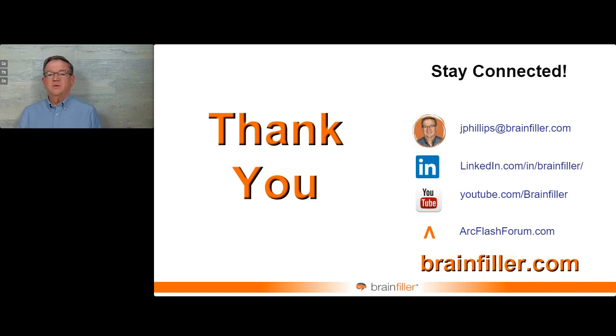Here's a really good one. There's currently a lot of virtual training replacing in-person training. Does virtual training satisfy all the requirements? Everything but hands-on. If you need hands-on to demonstrate skills, it's hard to do that virtually. But the 2021 edition of NFPA 70E says training could be classroom, on the job, or I think it uses the words computer-based training, virtual training. And that was before the pandemic. In 2021 we were right in the middle of it, but that language was actually submitted before the pandemic. When that happened, I was like, wow, somebody thought this through. We'd actually start switching over to virtual beforehand anyway. So according to NFPA 70E, computer-based training is acceptable unless you need the hands-on, somebody visually verifying that you're doing the tasks correctly.